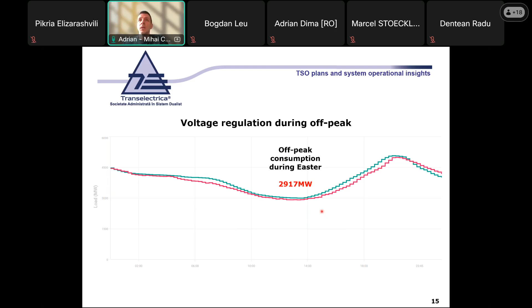To handle these operational constraints, we started some developments. The first ones try to handle the issues encountered with transiting flows. We plan to upgrade the 220 kV axis from Porțile de Fier, Reșița, Timișoara, Săcălaz, Arad to 400 kV. We plan to construct a new double-circuit overhead line, with just one circuit equipped, between Constanța Nord and Medgidia Sud. We plan to construct new overhead lines between Gădălin and Suceava, and between Gutinaș and Smârdan, and we plan to increase the transmission capacity of our 220 kV overhead lines by replacing the active conductor with a new one with increased section.